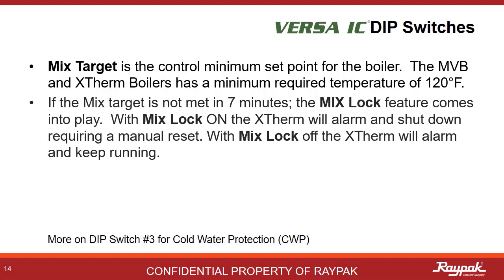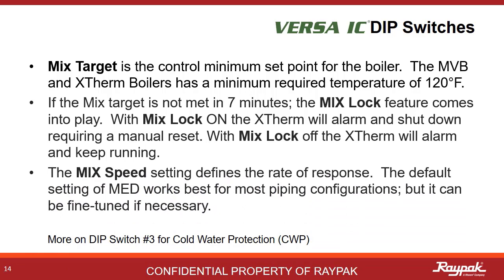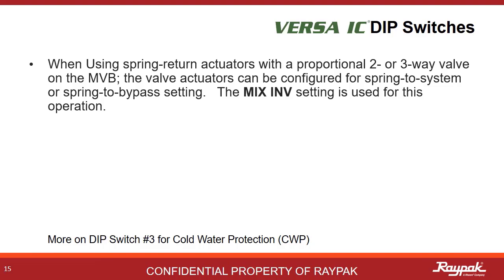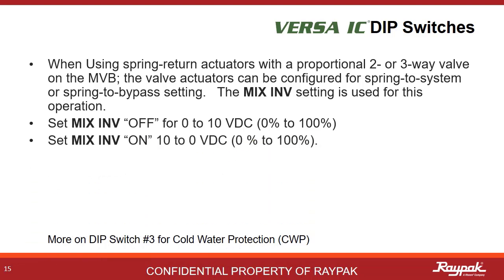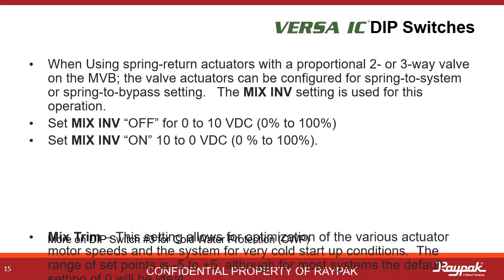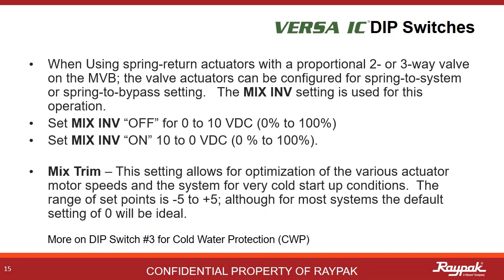The mixed lock setting determines whether the boiler alarms and keeps running or alarms and shuts off. The mixed speed setting is used for defining the rate of response of the cold water protection system — generally, medium is best. Mixed inverse is used to define which way the spring actuator works for the three-way valve used on the cold water protection system. Different manufacturers set them up differently. If the actuator responds with 0 to 100% open with a 0 to 10 volt DC signal, then set the mixed inverse to off. Mixed trim allows for a final fine tuning of the cold water protection system, scaled from minus 5 to plus 5, allowing you to give the system a little nudge one way or the other if necessary.